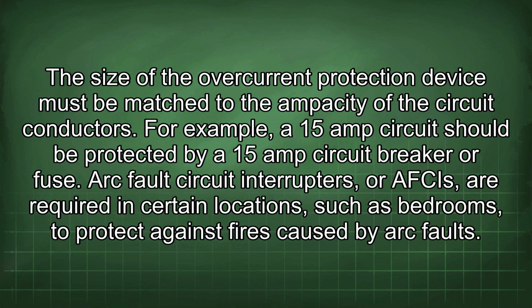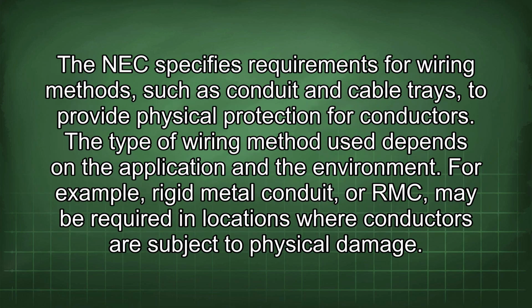The size of the overcurrent protection device must be matched to the ampacity of the circuit conductors. For example, a 15 amp circuit should be protected by a 15 amp circuit breaker or fuse. Arc fault circuit interrupters, or AFCIs, are required in certain locations, such as bedrooms, to protect against fires caused by arc faults. The NEC specifies requirements for wiring methods such as conduit and cable trays to provide physical protection for conductors. The type of wiring method used depends on the application and the environment. For example, rigid metal conduit, or RMC, may be required in locations where conductors are subject to physical damage.